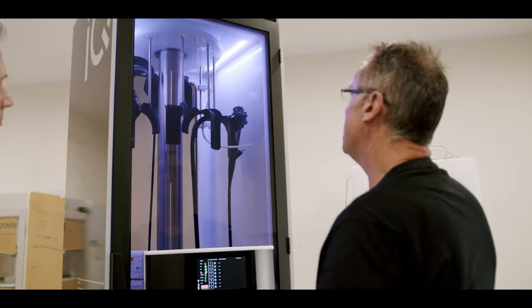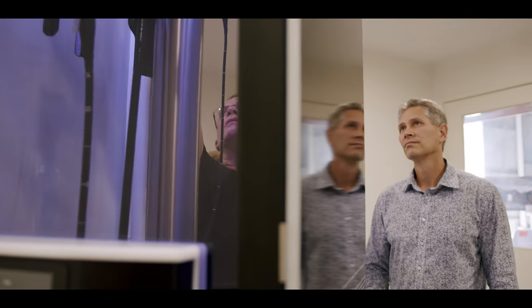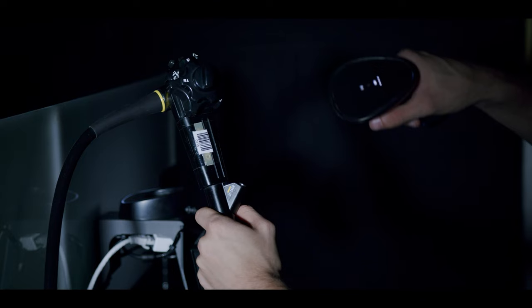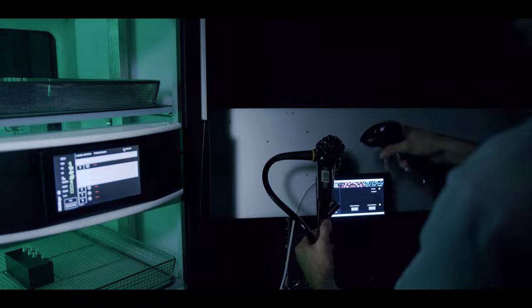The SmartLine endoscopy drying cabinets also provide tracking software allowing you to integrate the cabinet into any department, irrespective of the equipment you already have. This means we can work with any brand of washer you have now or in the future, future-proofing your department. The tracking software also uses barcode technology, meaning you can integrate it with your existing barcodes on your endoscopes.